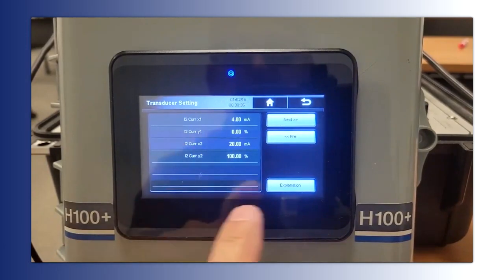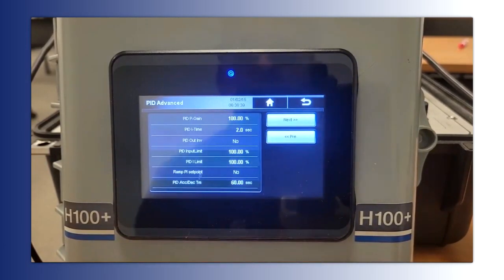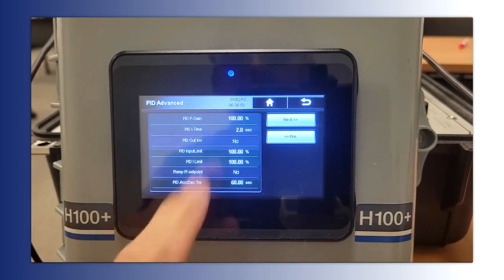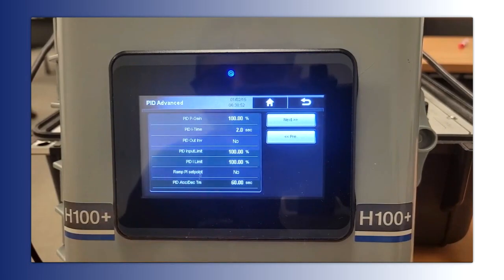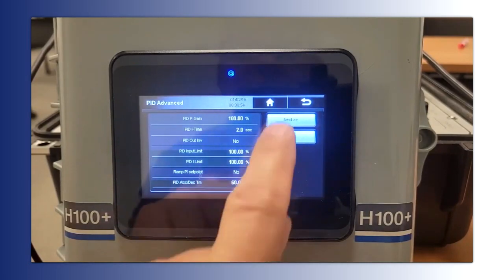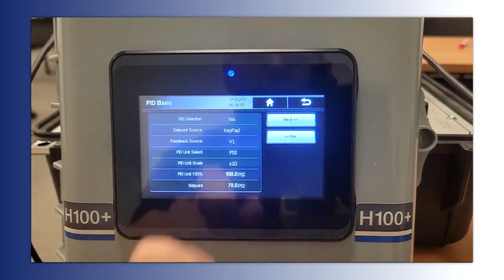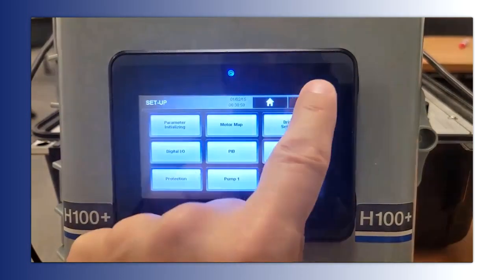Here you can do scaling for your analog inputs. Specifically, this is for 4 to 20. Here's your P gain and your I time if you wanted to adjust those two values to improve or change how your PID loop responds. We also have PID input limits and I limit. Those are for kind of limiting error and integral windup. And then now we're back to our main screen. So that's our basic PID stuff.